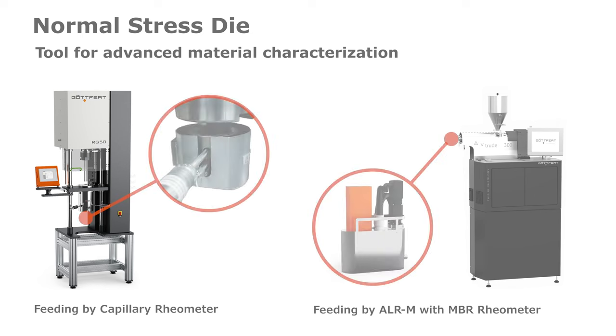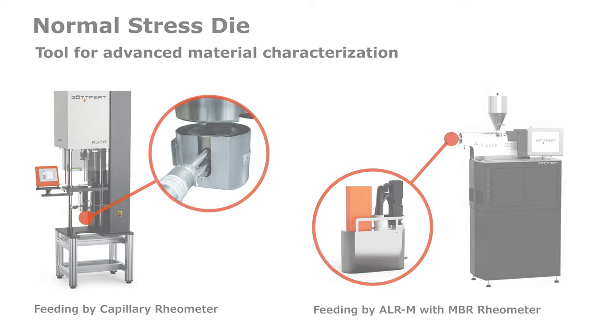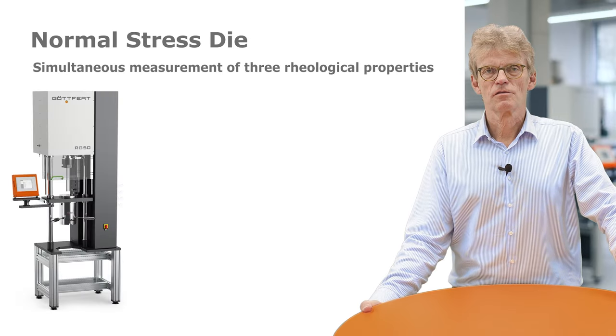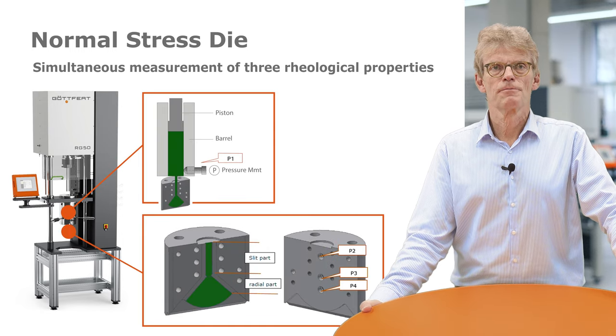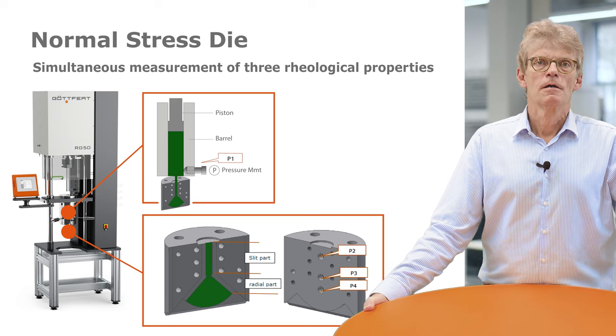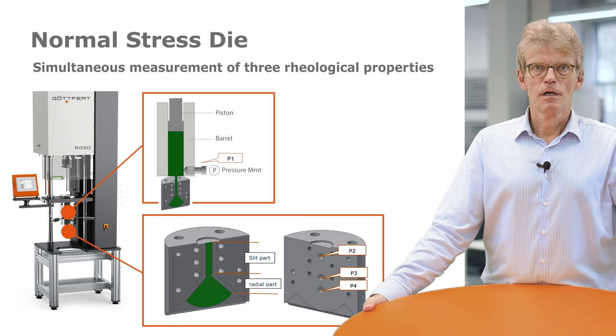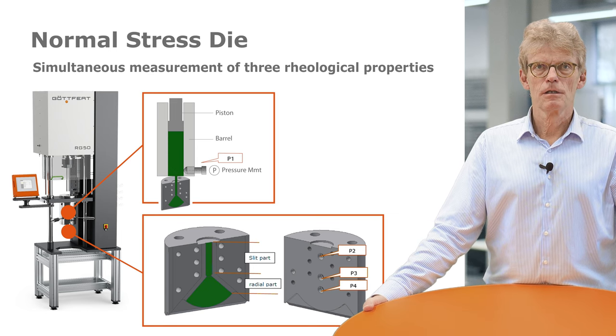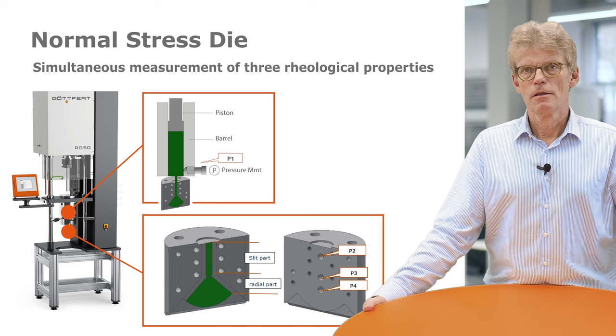The normal stress die can be placed below our capillary rheometer, just below the barrel instead of the usual die, or it can be located at the at-line rheometer MBR, also instead of a die. The normal stress die consists of a slit part and a radial part, which is a quarter of a circle.